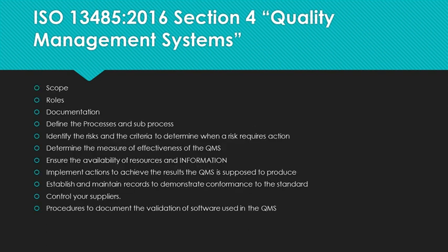Your first step in creating the Quality Management System is to decide how your organization will handle the following requirements. The scope: what is in the QMS and what is not? Think exclusions and not applicable clauses. You also want to define the limits of the work you perform. For example, if you are servicing equipment, which OEMs do you work on?